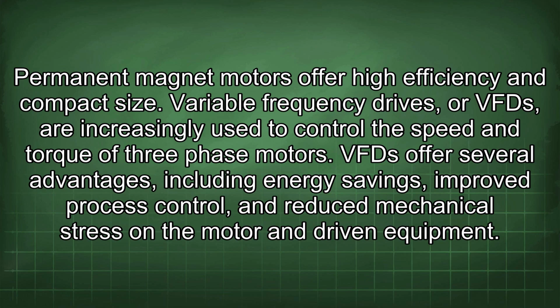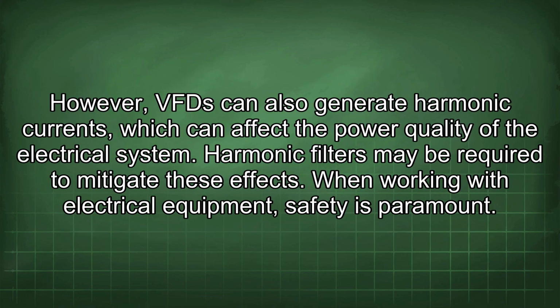Variable frequency drives, or VFDs, are increasingly used to control the speed and torque of three-phase motors. VFDs offer several advantages, including energy savings, improved process control, and reduced mechanical stress on the motor and driven equipment. However, VFDs can also generate harmonic currents, which can affect the power quality of the electrical system. Harmonic filters may be required to mitigate these effects.